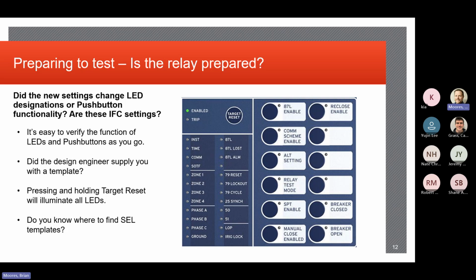We'll get a little bit to that in the end-to-end testing one on Thursday, I think. That's a little bit different scenario because you've got two relays, they have a pilot channel between them. They're communicating to each other, looking at a line, and we're doing some synchronized testing. And we will use the SER data from both ends to make sure that they're doing what they're supposed to be doing, especially in a blocking scheme or permissive scheme where you want to put a fault that's not on the line, right? One relay is going to see if it's forward looking, but it's going to be beyond the other relay. Both relays are still going to see it, but one's going to say, no, it's behind me, don't trip, to the other guy.